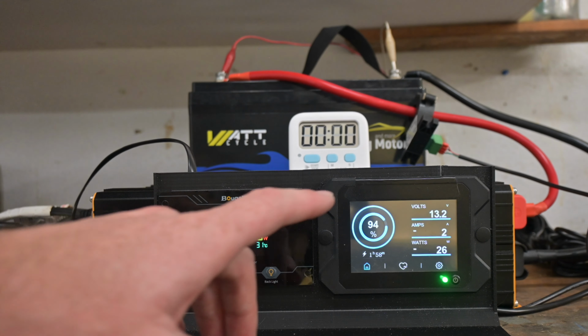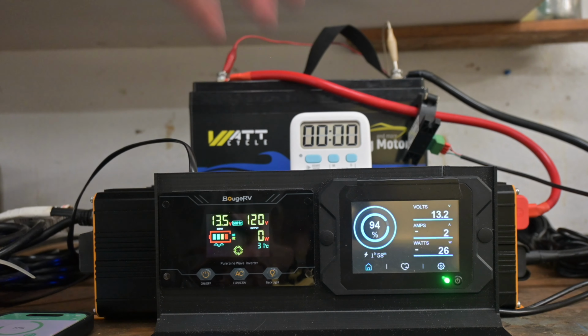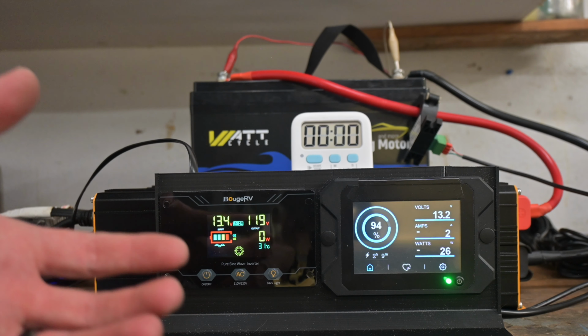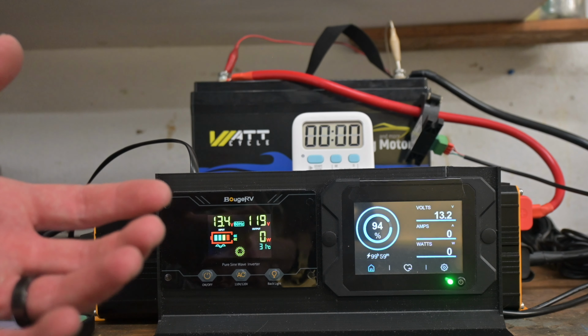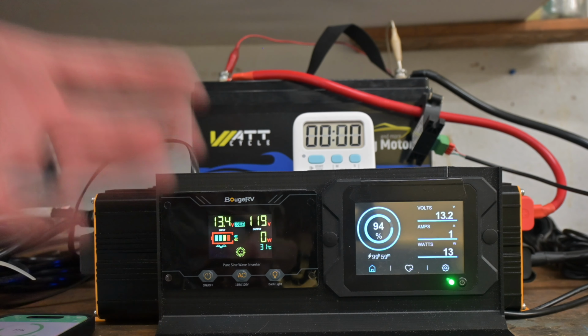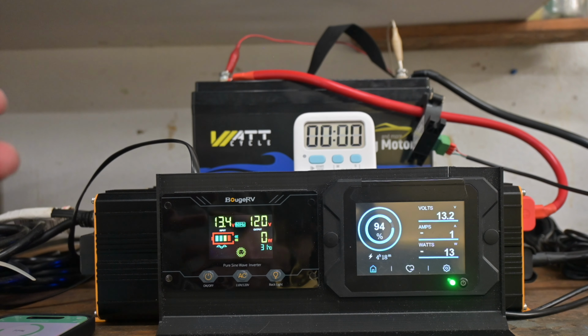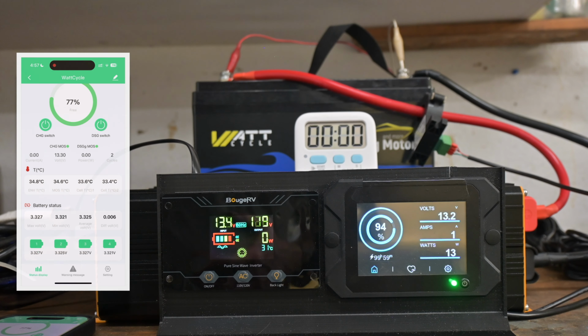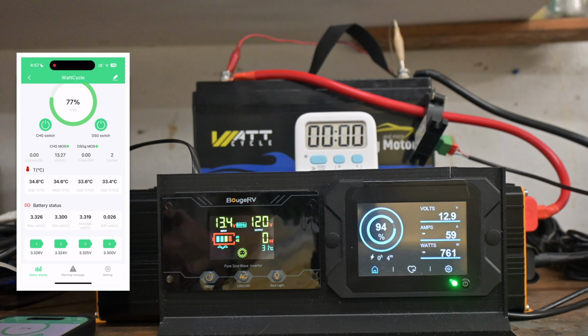Once it hits over 100 amps, I'm going to start the clock. What we're looking for is the continuous discharge disconnect. It should disconnect after, I don't know, 3 to 5 seconds over 100 amps. Let's see if that's going to play out that way. So without further ado, I'm going to turn on the first heater here and get ready to start our test.